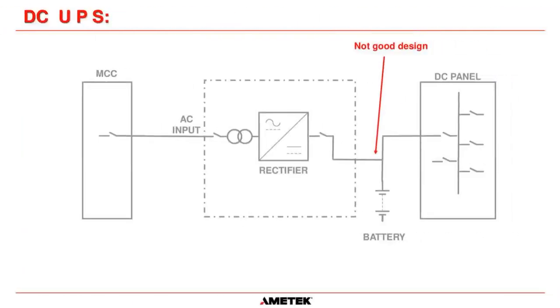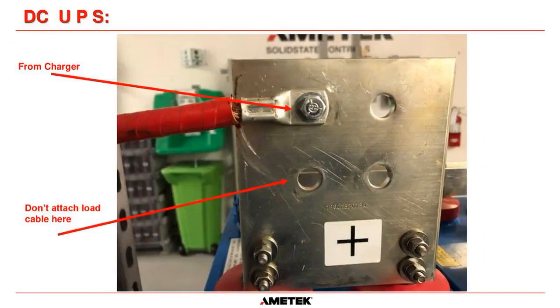And another poor design is when they connect the output cables of the charger and the load cables onto the battery terminals. Once again, you can't see it very well with this single line diagram, but you can see here that there's a very large terminal plate here. You can see the battery is down here, and there are 3 spare holes on this. So a lot of people say, okay, well, why don't I attach my load cable here?